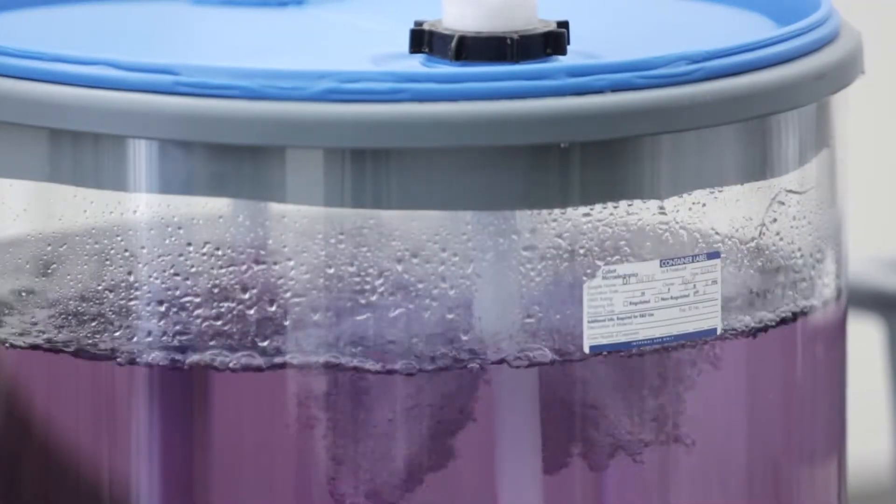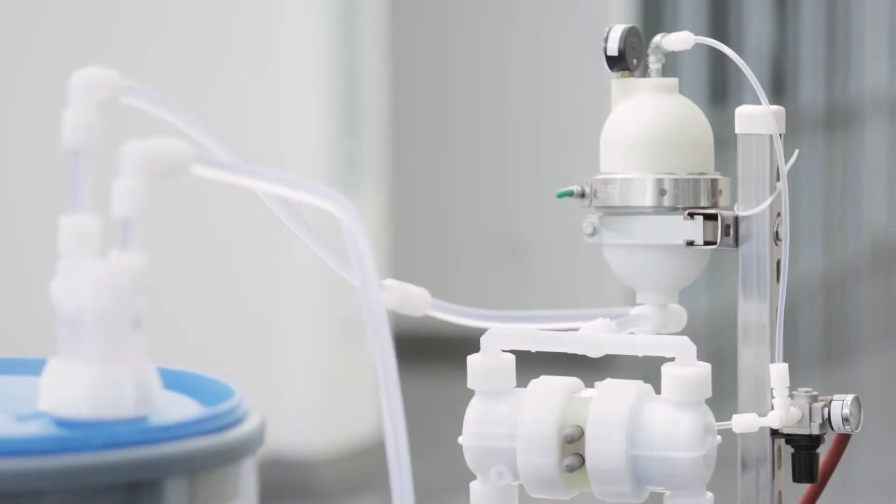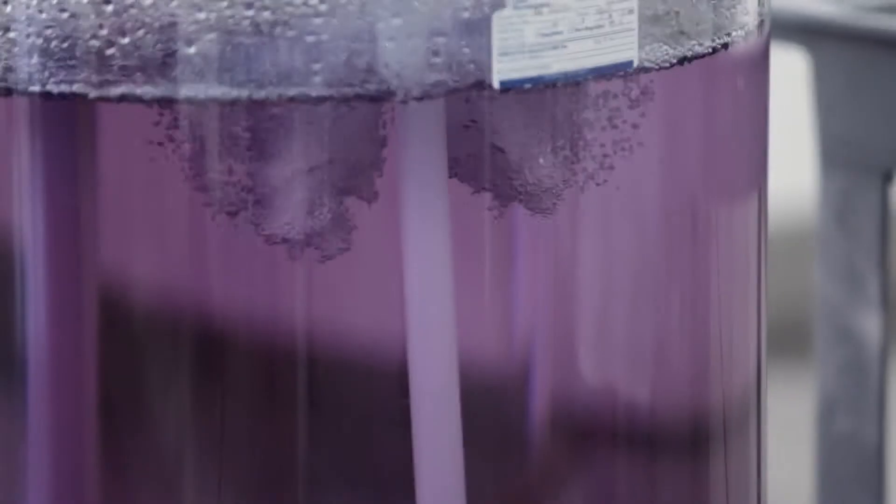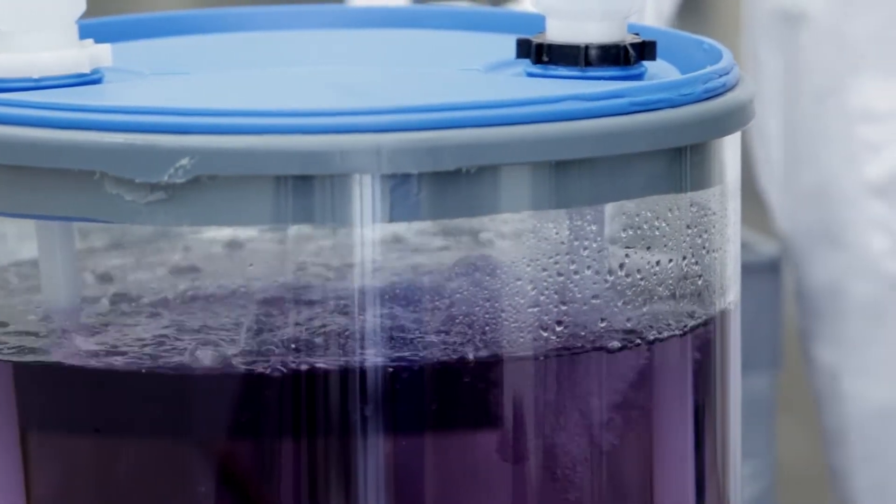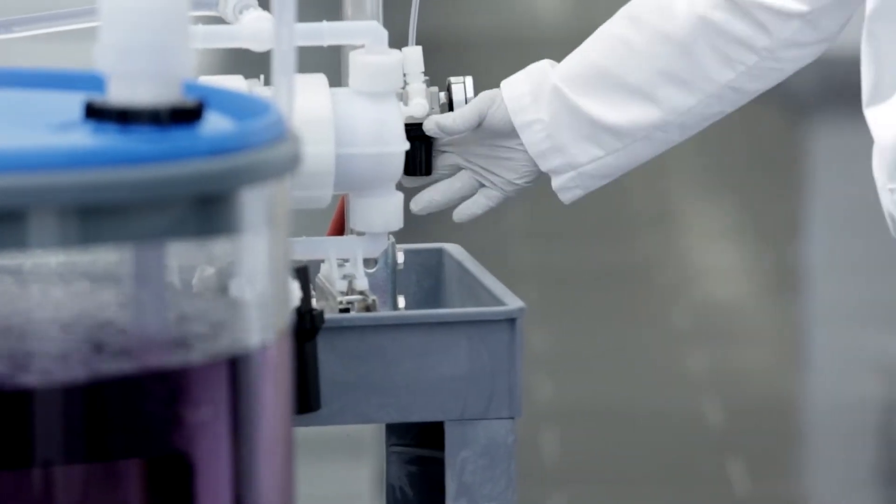So as you can see, there's a tremendous amount of shear from the slurry going back through the half inch fitting, through the tortuous path inside the dispense head and out the small orifices and being injected back into the drum at high velocity and literally spraying back into the container. This type of recirculation can damage delicate slurries, especially those with fumed silica or some polymer components, and it can cause extreme foaming. I won't demonstrate that with this configuration. I'll show you what that looks like a little bit later on with a different dispense head and return combination.